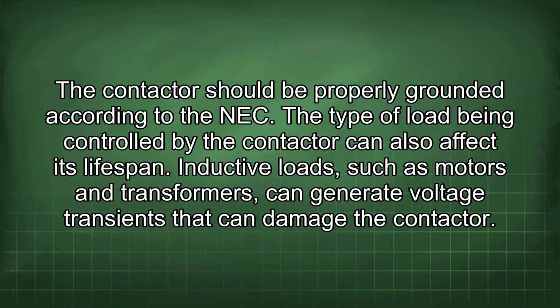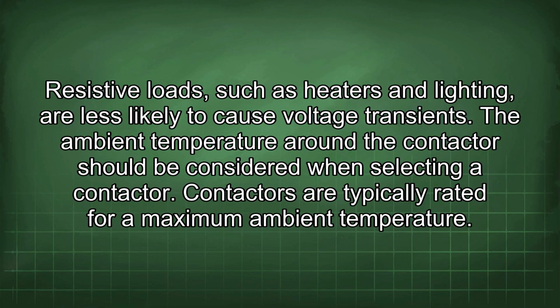The type of load being controlled by the contactor can also affect its lifespan. Inductive loads, such as motors and transformers, can generate voltage transients that can damage the contactor. Resistive loads, such as heaters and lighting, are less likely to cause voltage transients.